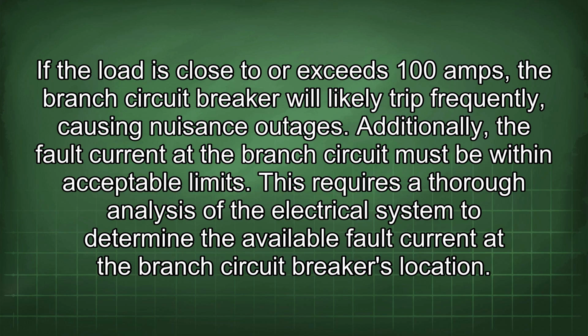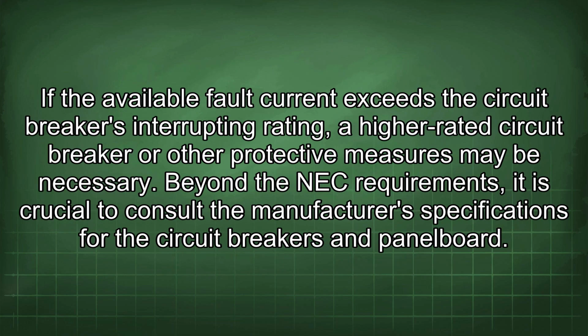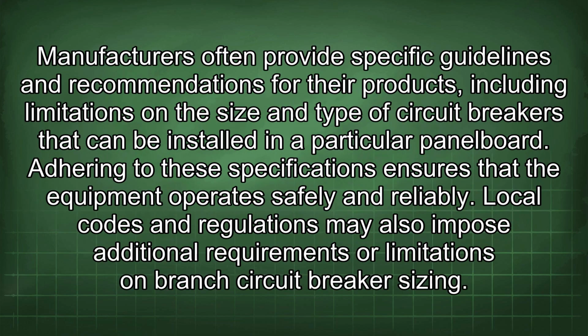This requires a thorough analysis of the electrical system to determine the available fault current at the branch circuit breaker's location. If the available fault current exceeds the circuit breaker's interrupting rating, a higher rated circuit breaker or other protective measures may be necessary. Beyond the NEC requirements, it is crucial to consult the manufacturer's specifications for the circuit breakers and panel board. Manufacturers often provide specific guidelines and recommendations for their products, including limitations on the size and type of circuit breakers that can be installed in a particular panel board. Adhering to these specifications ensures that the equipment operates safely and reliably.